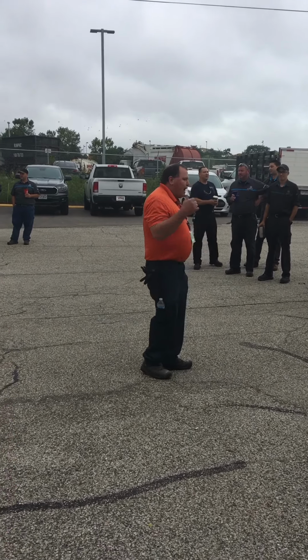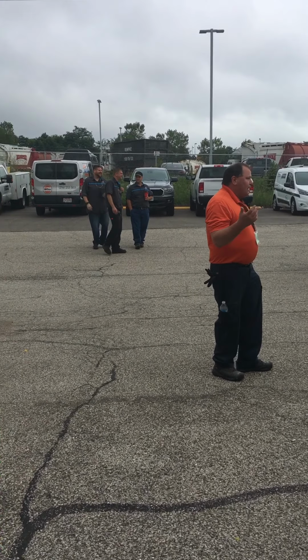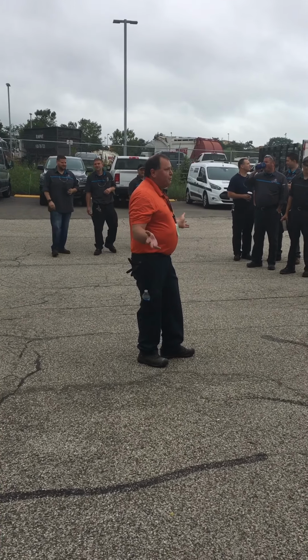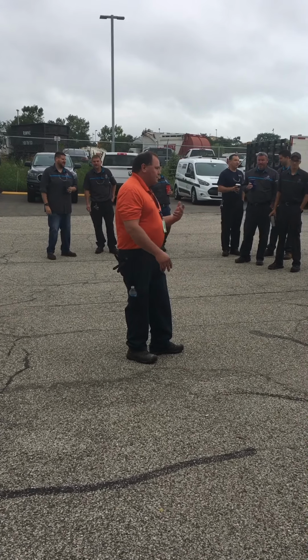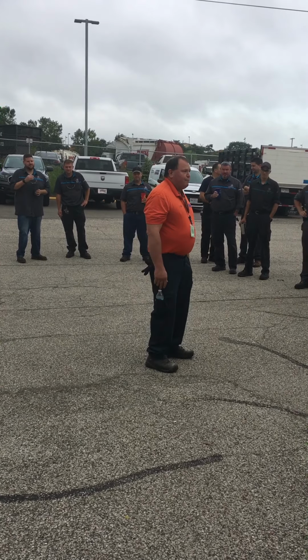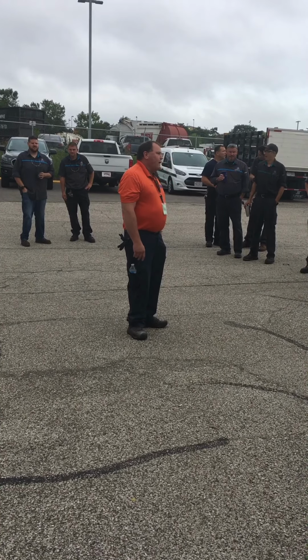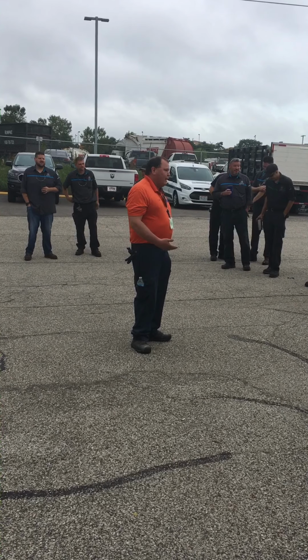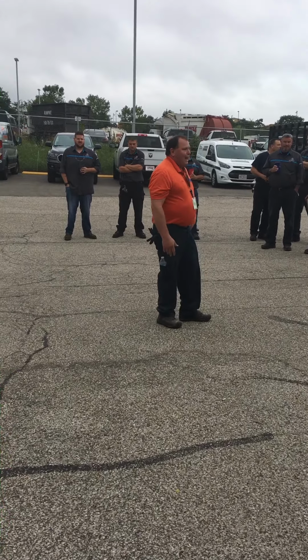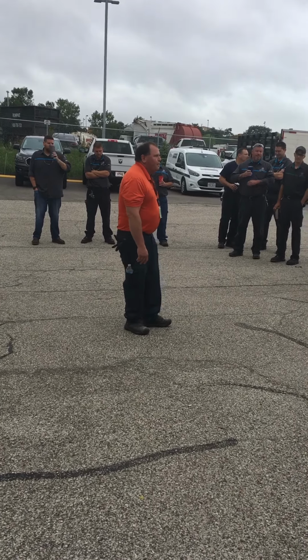Well, the only ratings that one's not rated for are Class D or Class K. K is a kitchen fire, like a grease fire. What it's going to do is splash the grease and spread the fire because of the pressure coming out. Class D fires, I've actually heard of them burning so hot that they will burn the chemical that's in that extinguisher. That's why those extinguishers have a special chemical in them. Usually it's either sand or copper that covers it, and it's not as likely to burn, because metal fires burn extremely hot.